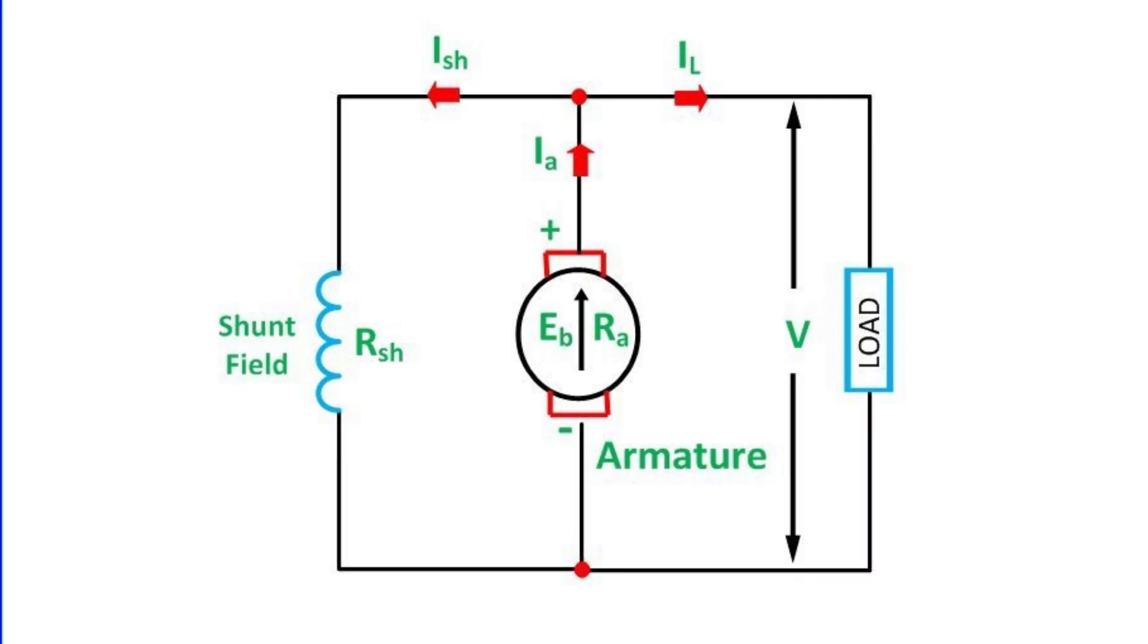This is where the shunt field winding comes into play. Connected in parallel with the armature, the shunt field winding creates an additional magnetic field that interacts with the armature's field. By adjusting the current flowing through the shunt field winding, we can control the strength of the overall magnetic field and, consequently, the generator's output voltage. But how do we determine the precise resistance needed in the shunt field circuit to achieve stable voltage generation? This is where the concept of critical field resistance emerges as a key factor in understanding and operating DC shunt generators effectively.